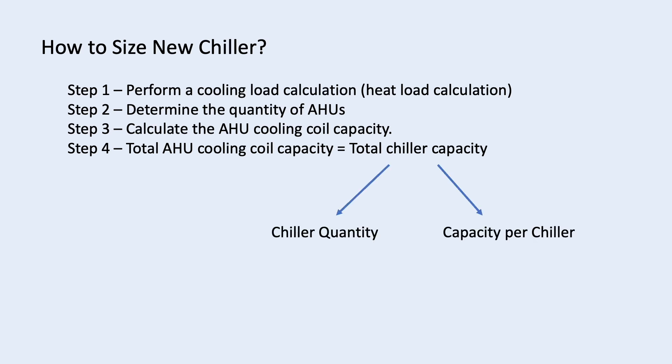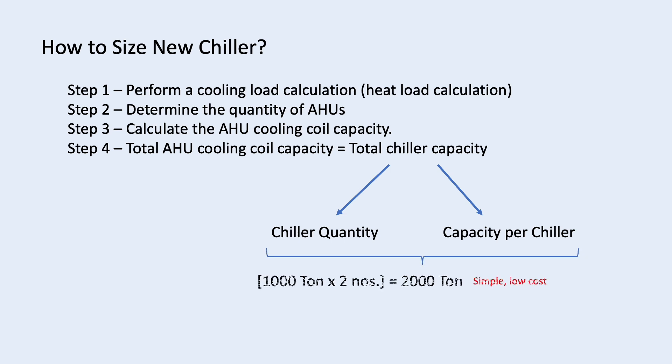After that, we need to determine how many chillers we need and what is the capacity of each chiller. Different combinations have different advantages. For example, if you need 2000 ton, you may use 2 chillers with each at 1000 ton. Less chiller is simple and cheaper.